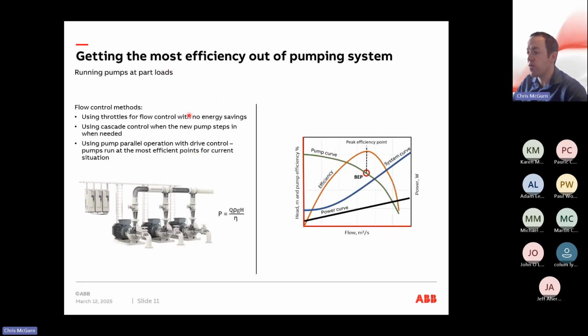So how do people run their systems at part load? There are different ways of doing this. Traditionally, in a pumping system, people would have used mechanical systems to slow down the speed of the fluid that they're pumping. They would have used throttles, mechanical butterfly valves, that type of thing, which physically slows down the water and the flow. But the problem with that is that the motor and pump behind it are actually still running at full load, just trying to push past the blockage that the throttle puts in place in the pump. So they are still running at relatively high loads when the requirement from the system is only maybe 70, 60, 50%.